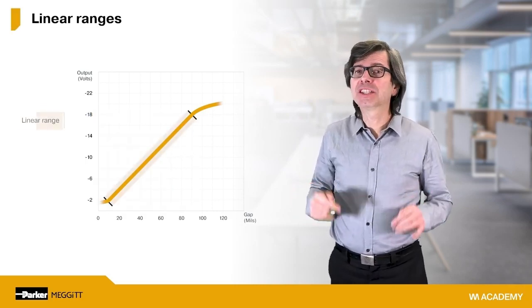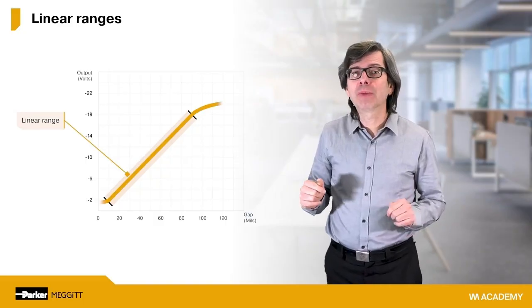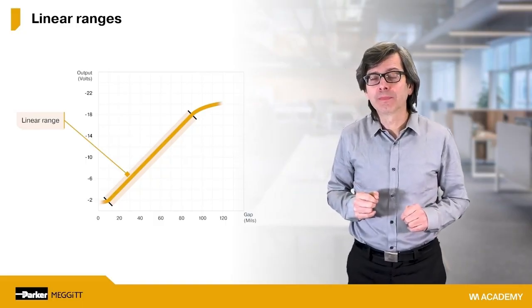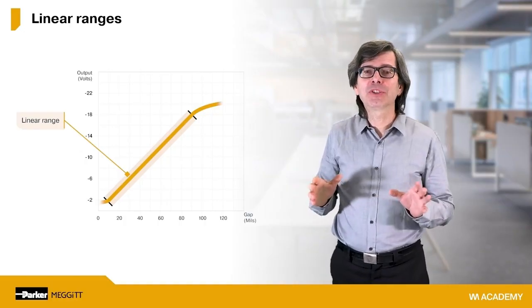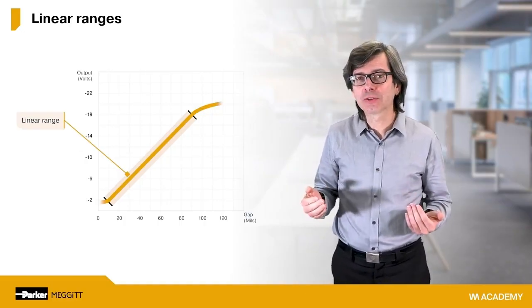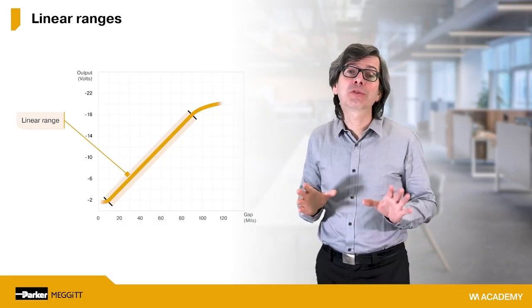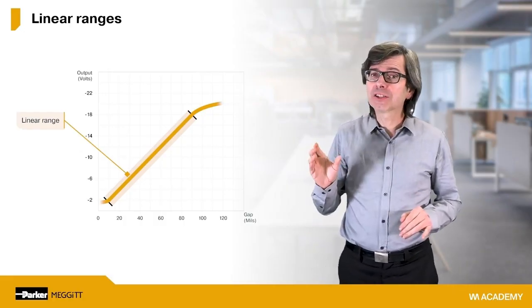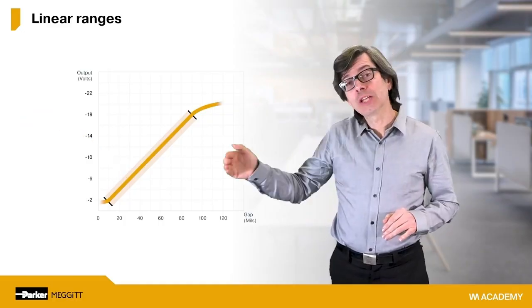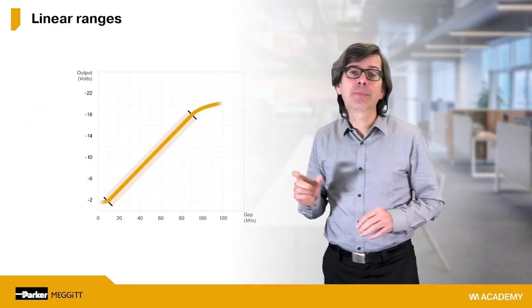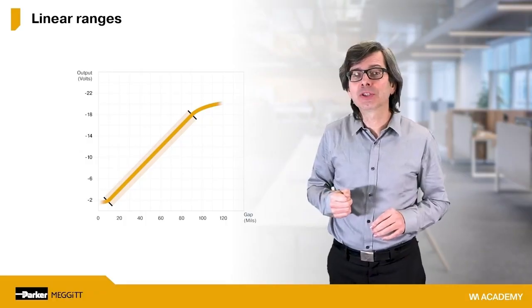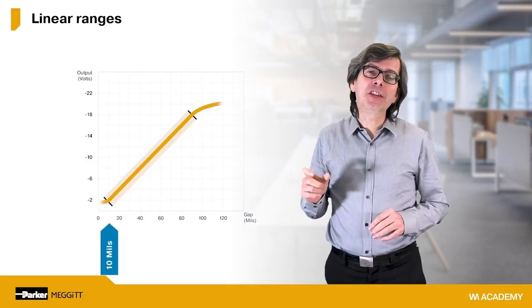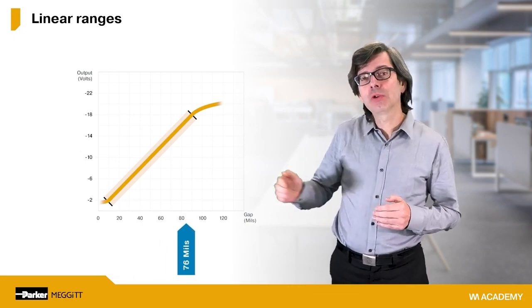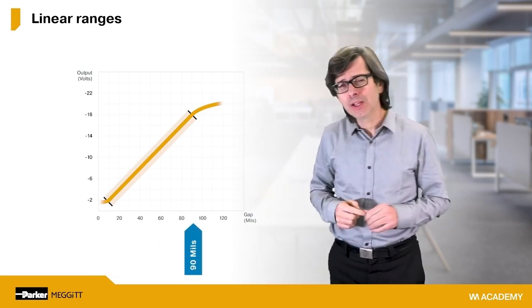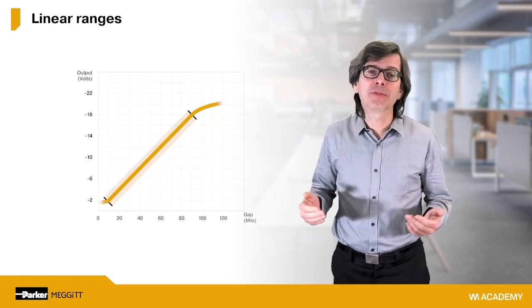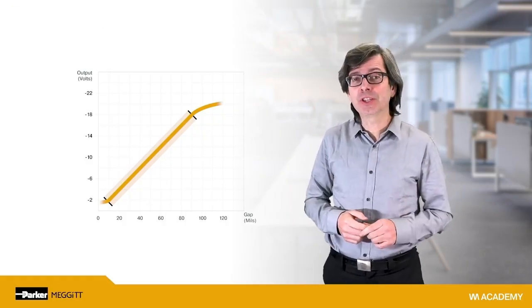Probe systems exhibit a linear range as shown by the shaded area of the yellow line. Inside the linear range, the probe system delivers a consistent scale factor that is accurate within factory specifications, regardless of where we are along the line. In this example, the scale factor is 200 millivolts per mil, and the linear range stands from 10 mils to 90 mils. Different probe systems will exhibit different scale factors and different linear ranges.